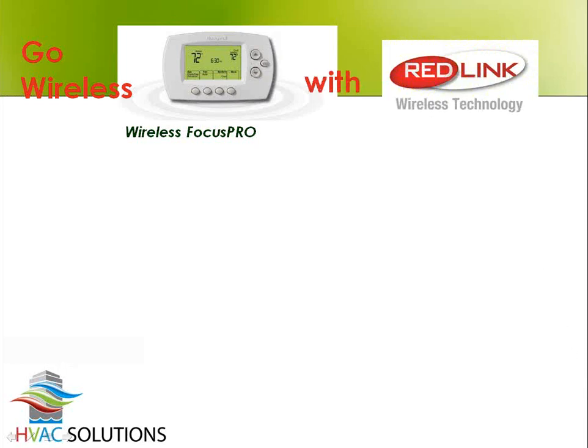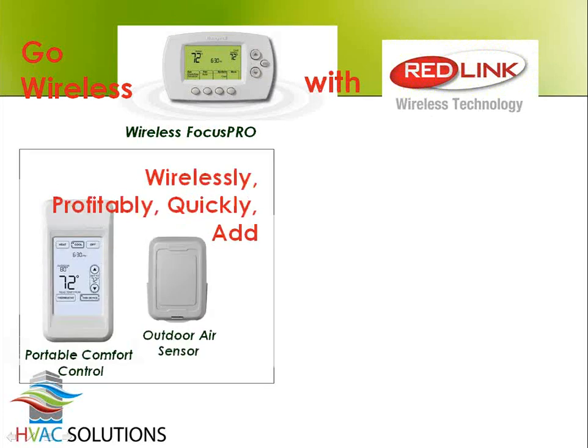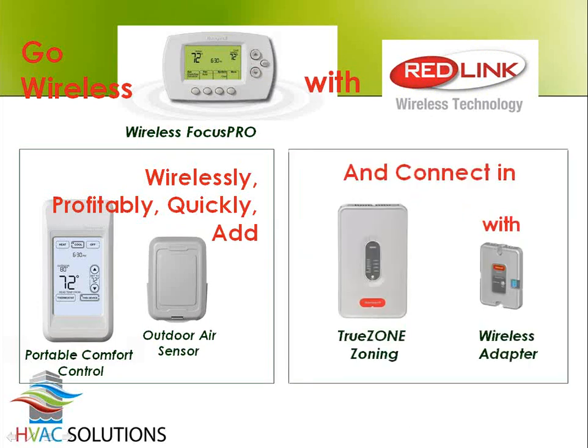All right, so the wireless FocusPRO is one way to do it, like we said. The same portable comfort control and outside air temperature sensor that work with FocusPRO work with the Prestige. And as you remember, the difference is the FocusPRO is 100% wireless, no wires. In addition to talking to an equipment module that controls a furnace and or a humidifier, you can also have it work with a zoning system.